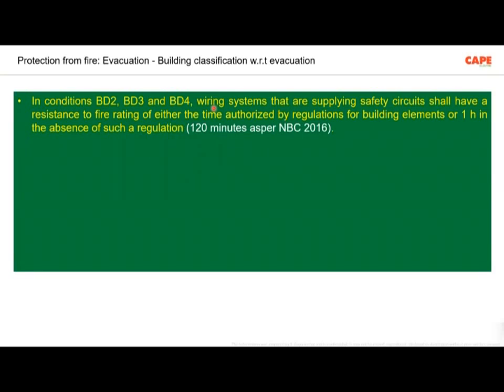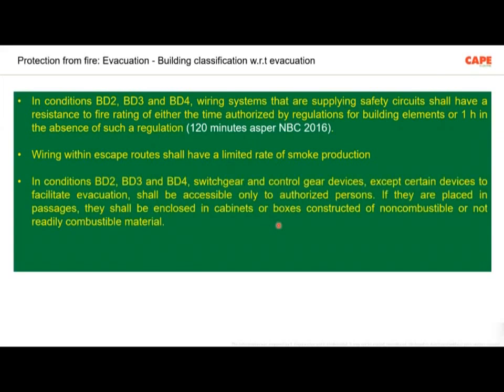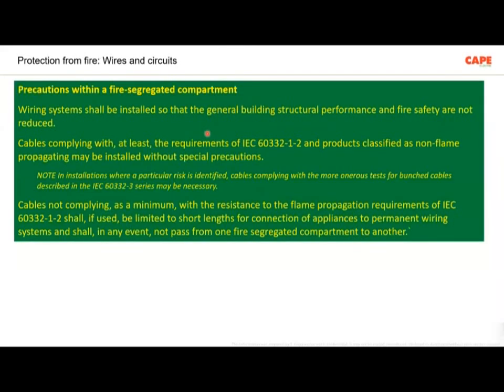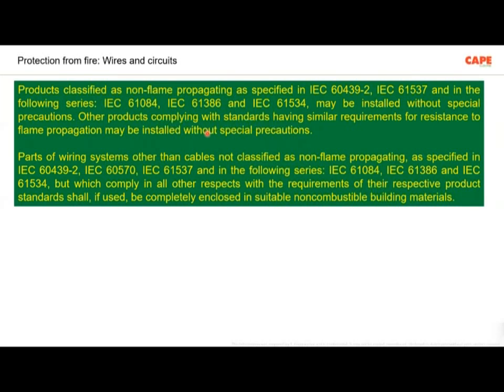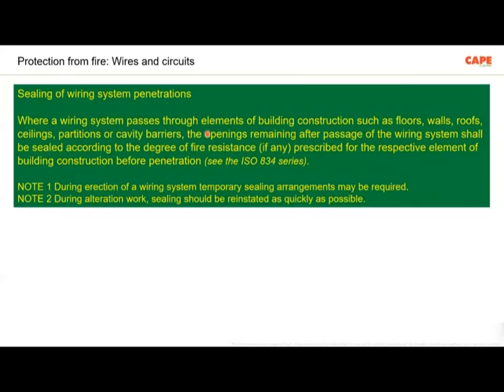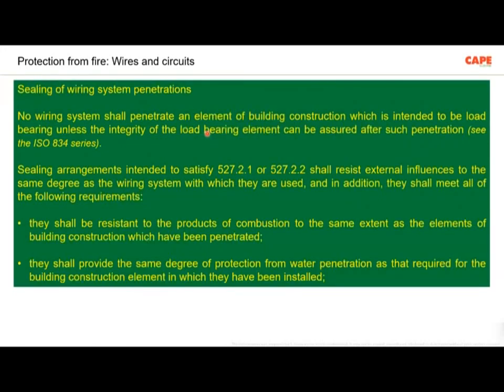It is not only the wire. Please understand, there is a new IS code for fire resistant wires, but using the wire alone will not ensure safety. The entire electrical wiring, the fixing materials, the distribution board, the entire system should have a functional guarantee of 120 minutes. I would say 120 minutes is a little bit higher. Even 60 minutes or 1 hour itself is enough. But anyway, it is the subject of the National Building Code. So like this, a lot of additional safety measures are necessary. I skip these points. Anyway, the presentation is available. We will send it to you in the mailer. You can take it, or you can simply go to IS732 clause number 4.3. All these parts are explained. I skip some of them.